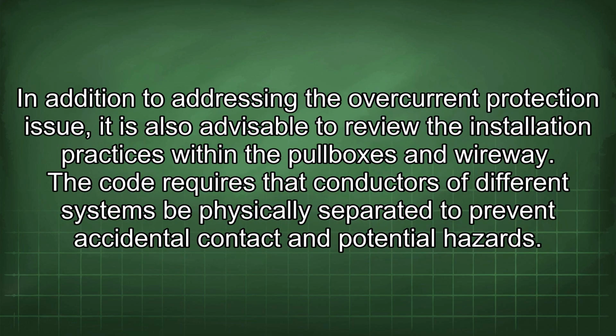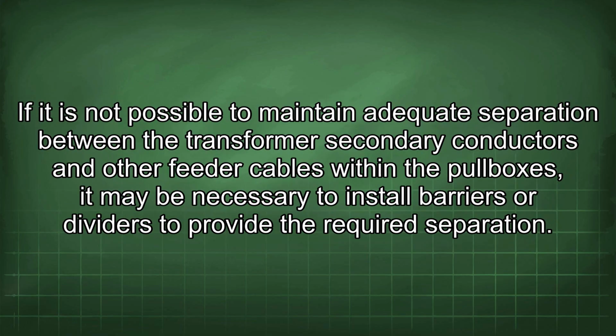In addition to addressing the overcurrent protection issue, it is also advisable to review the installation practices within the pullboxes and wireway. The code requires that conductors of different systems be physically separated to prevent accidental contact and potential hazards. If it is not possible to maintain an adequate separation between the transformer secondary conductors and other feeder cables within the pullboxes, it may be necessary to install barriers or dividers to provide the required separation.